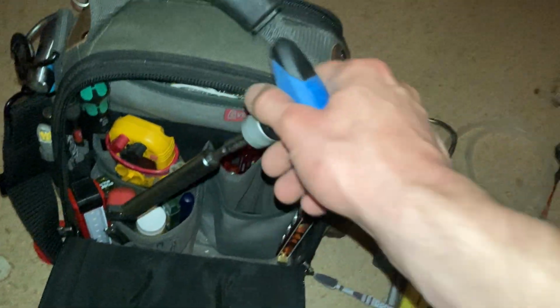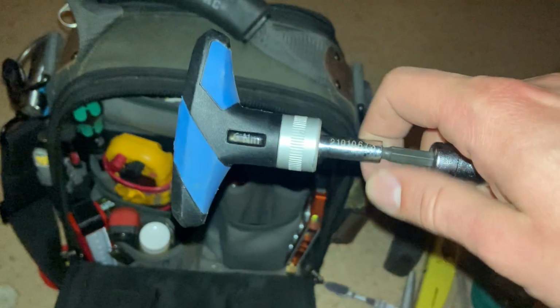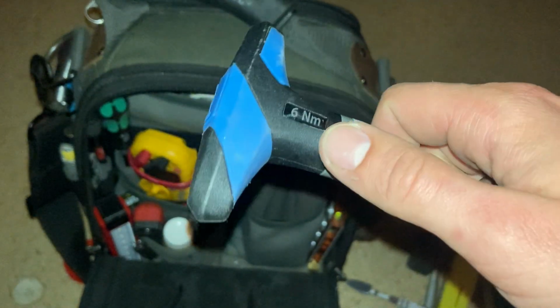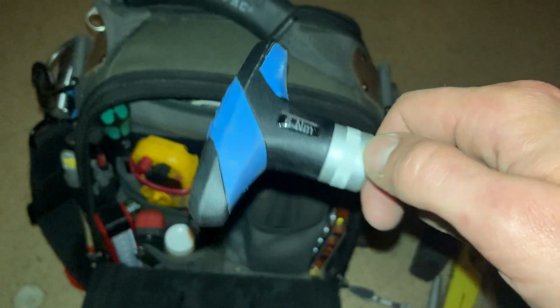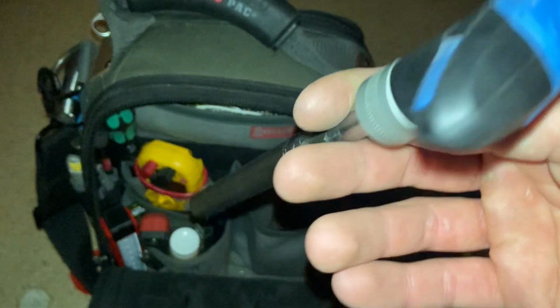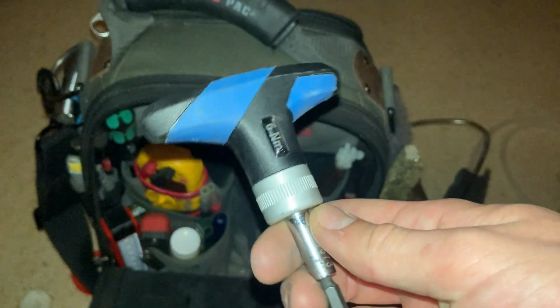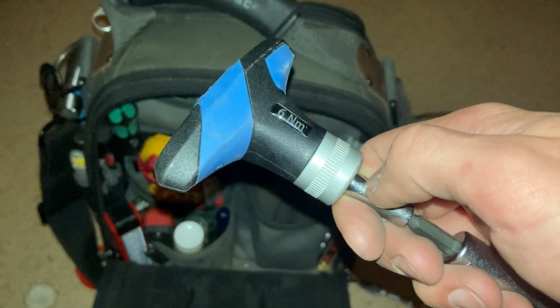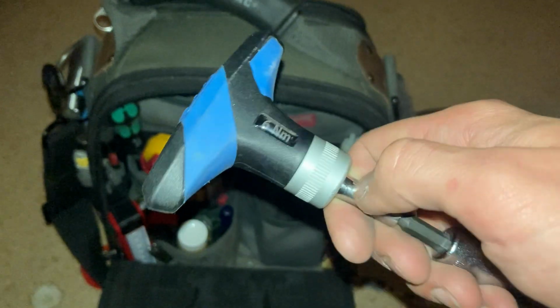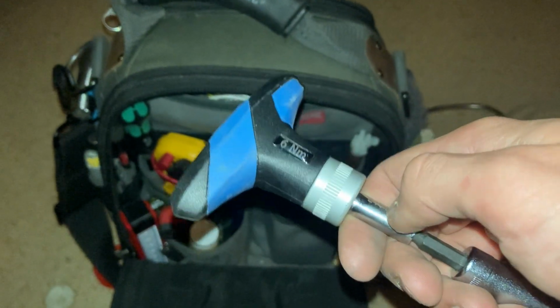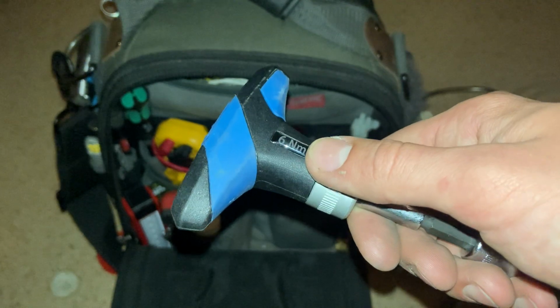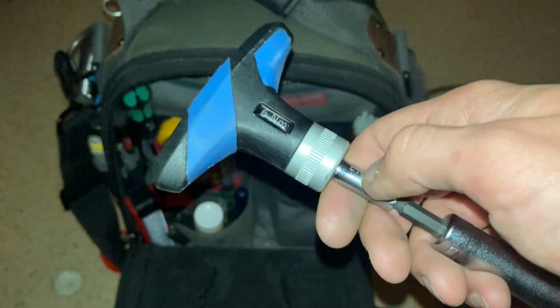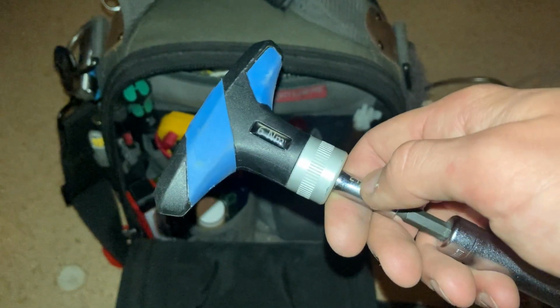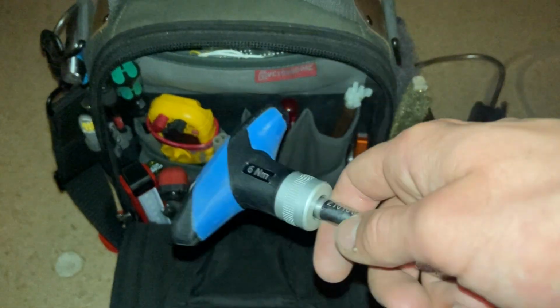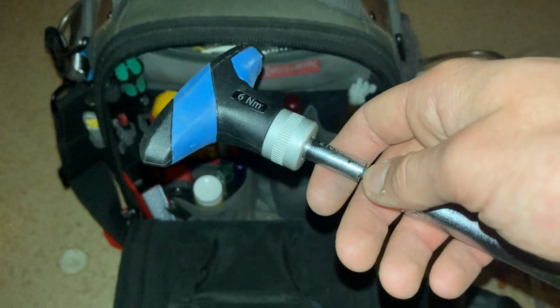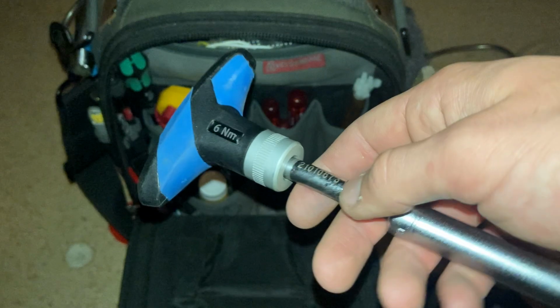This one was a tip from my buddy Ranch, the bearded plumber. It's a 6 Nm torque wrench, so it's only for tightening, which is the exact amount you need on the Nefit Bosch Pro line. All Verdens are 6 Nm, and the Remeha Avanta is 7 Nm, but the difference is so little. If you put a new gasket in, you put 6 Nm, it's gas tight. The Avantas and Remehas are usually just tightened with my nut driver.